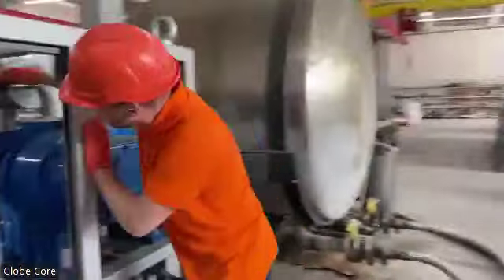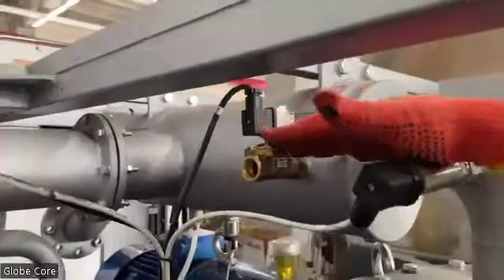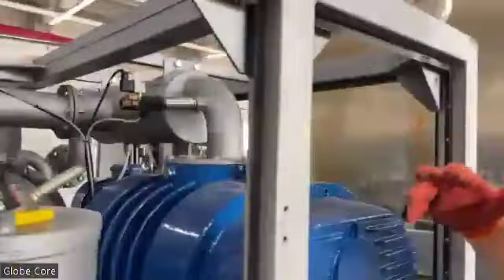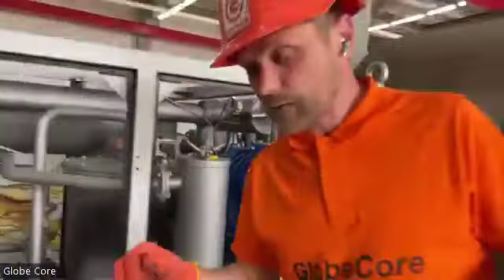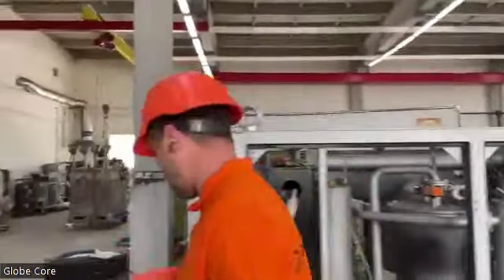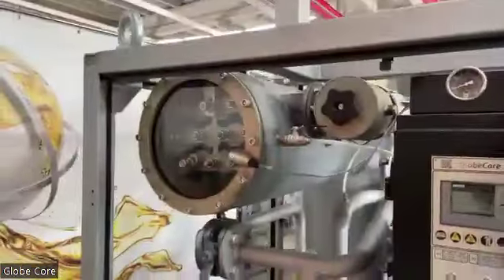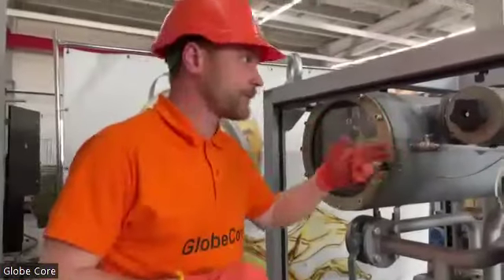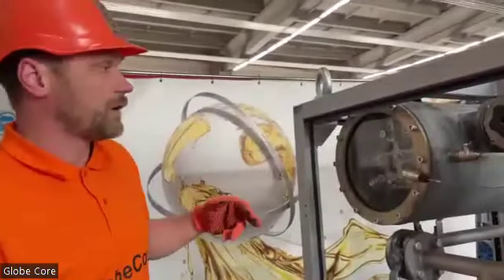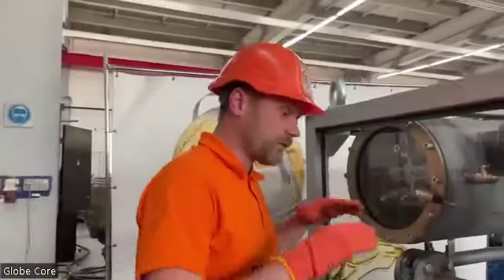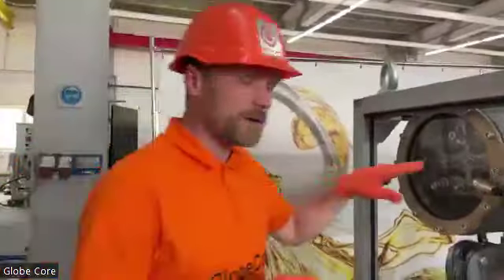If foam is detected by this sensor, the system automatically opens the solenoid valve, which is over there. It is in the vacuum trap. By means of this, we raise pressure inside the vacuum chamber, and in this way, we fight foaming. So, if the foam sensor detects foam, it opens the air inlet solenoid valve, pressure rises, and foam level decreases. It is done automatically.